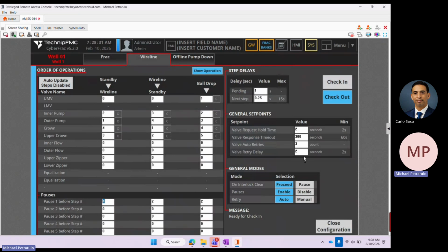And then here on the right side we have a couple of somewhat useful things. This pending setting - if I made this 10 seconds, when the phase change request is approved, the sequencer will wait, it'll pend for 10 seconds before it starts the very first step. So it'll just say pending, wait 10 seconds, and then the first step executes.